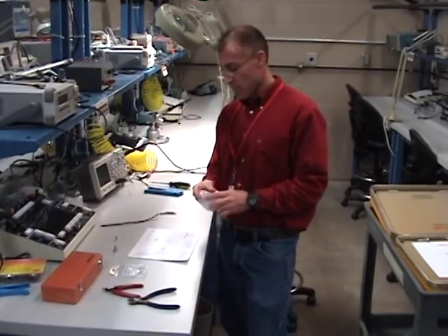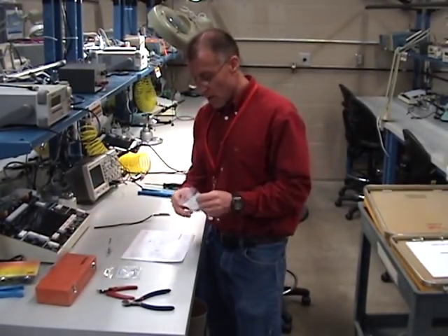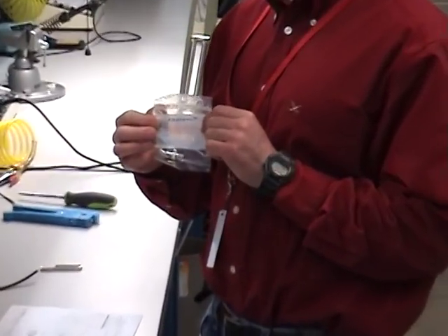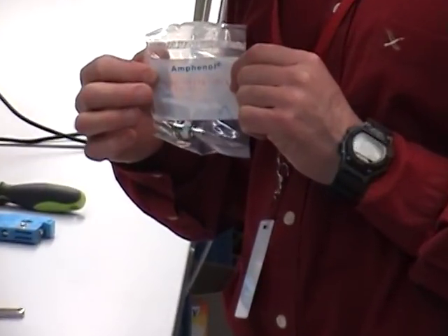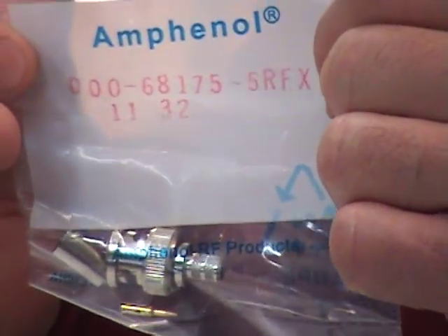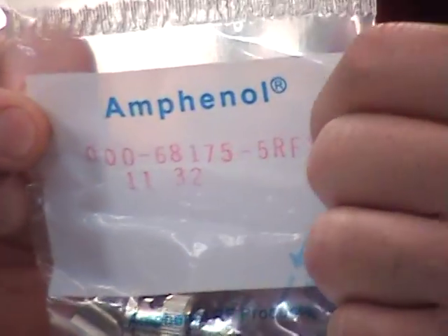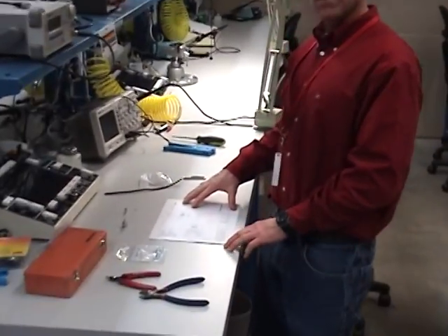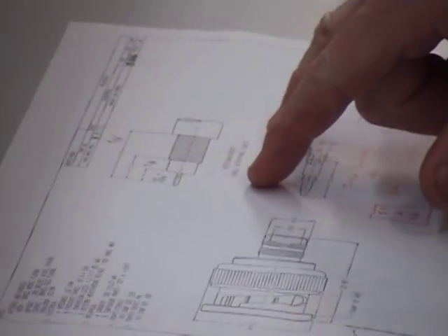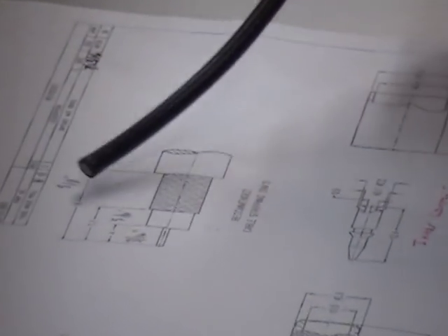These are RG59 BNC. That's important to know because when I order these, the first thing I need to know is the part number. When I look at the part number of this series connector, it will give me a spec sheet. On my spec sheet, I wrote myself a couple notes, so it saved me a little time. But on the spec sheet or data sheet, it will give me the stripping dimensions. And that's the thing you need. In many cases they're the same, but several times they're different, especially on different cables.